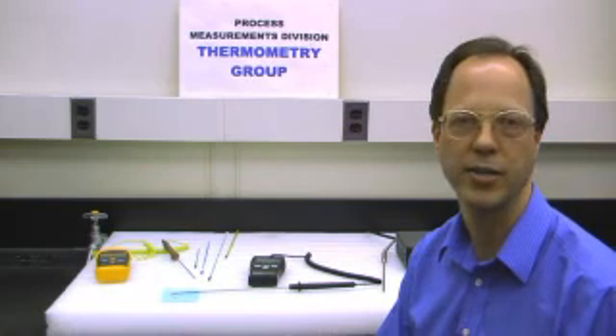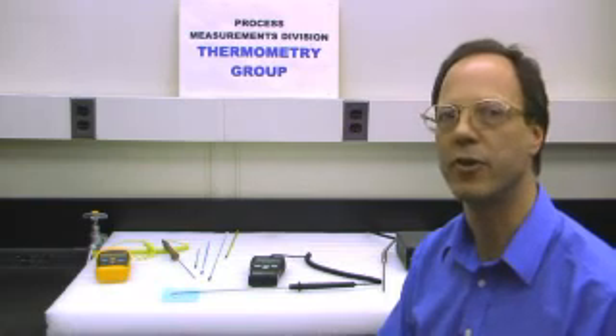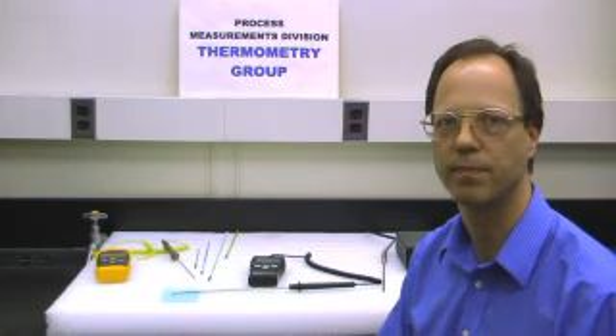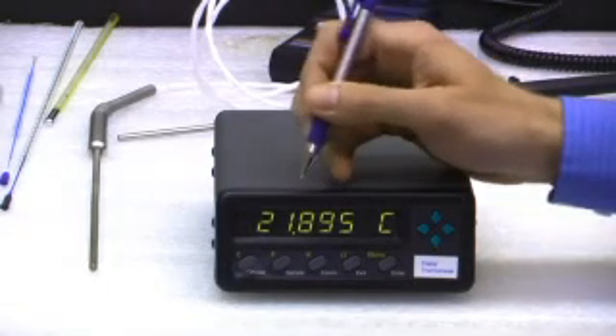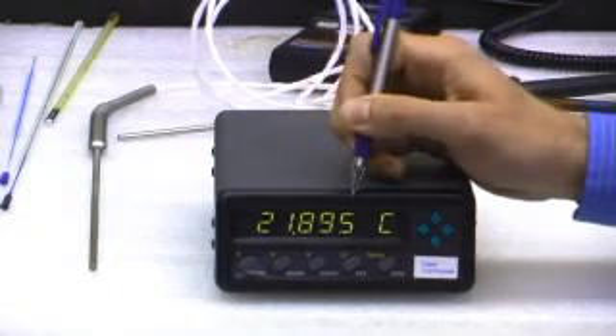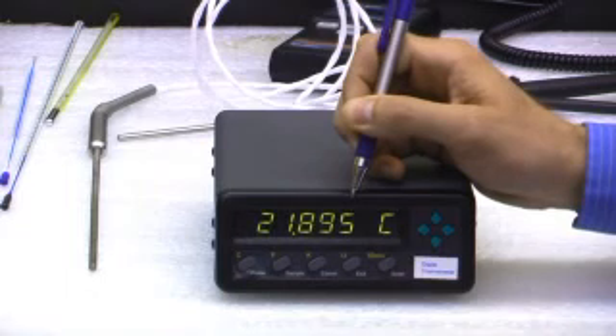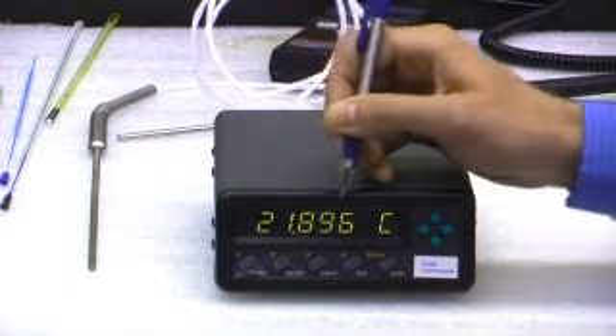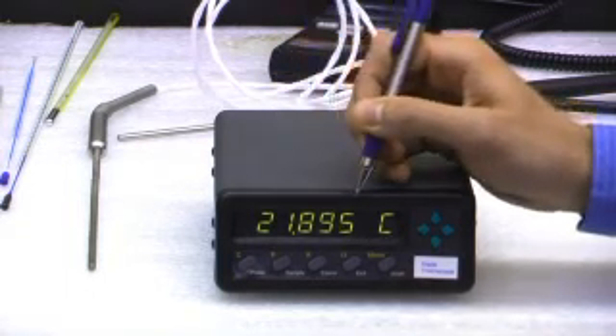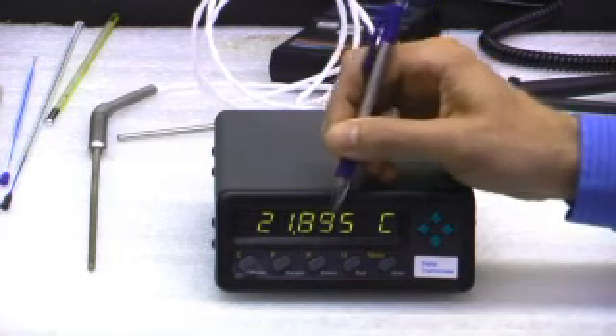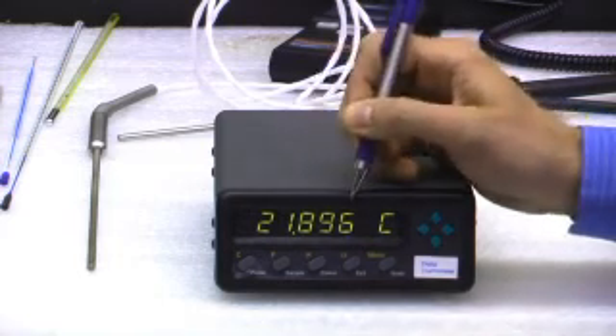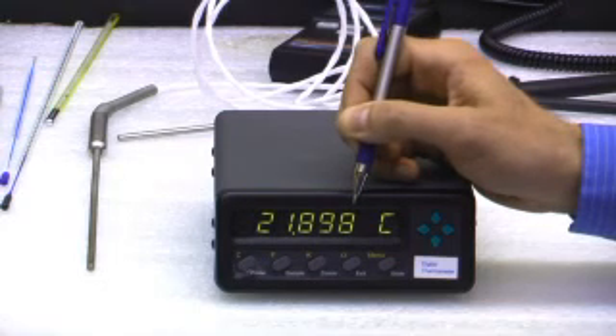Electronic thermometers cost more than mercury thermometers. On the other hand, they're easy to read and easy to automate. Often that gives you reduced cost of usage. Here's a readout that goes all the way to 1/1000th of a degree Celsius. All these digits can be misleading. Remember that just because it has this many digits doesn't mean that the probe together with the readout has the accuracy indicated by this last digit.